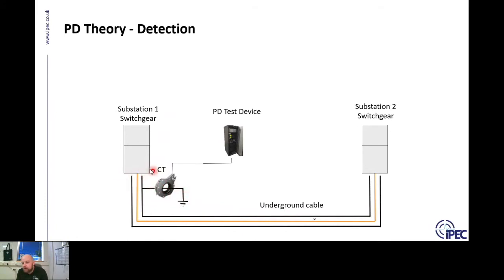The signal travels along the inside of the earth sheath, gets to the switchgear termination, where the earth is isolated from the switchgear, and travels through the HFCT. This is key: in order to detect a PD along the earth, we need that earth to be isolated from the switchgear. If the earth is connected to the switchgear, the PD signal will go into the switchgear and be lost — we won't be able to detect it through the HFCT.